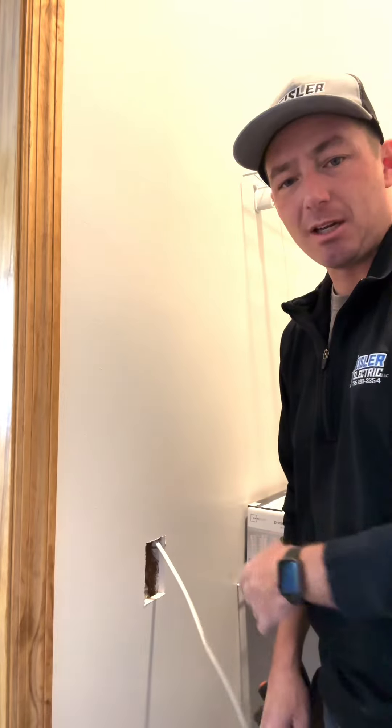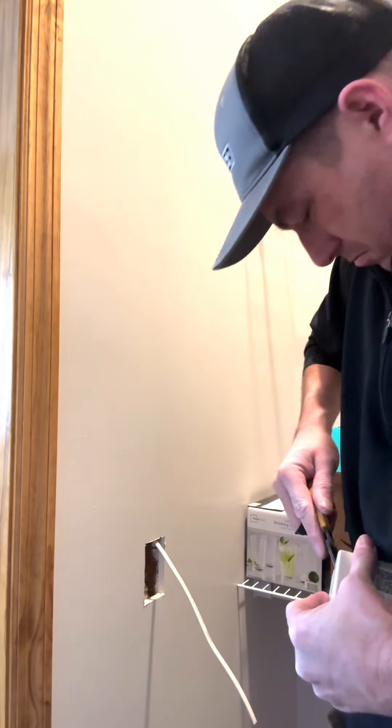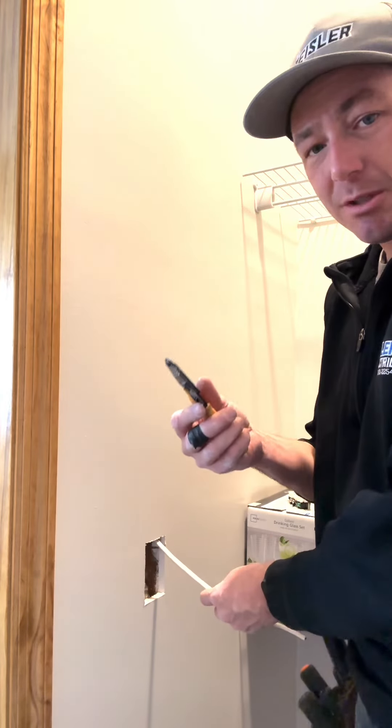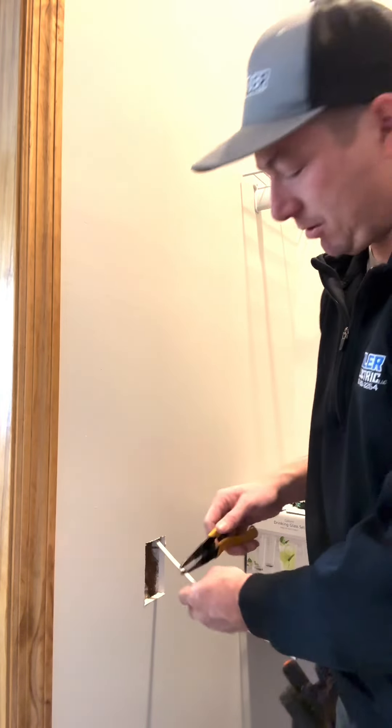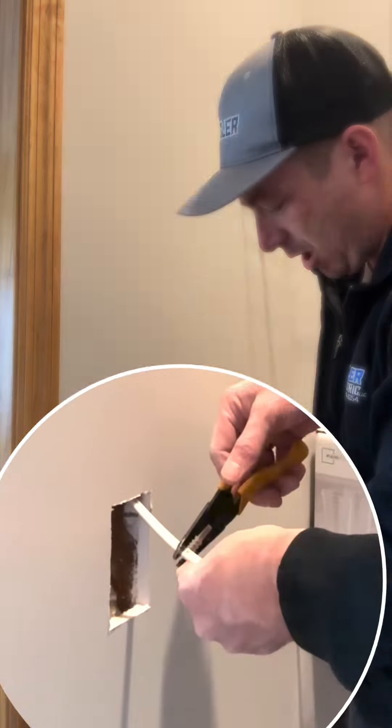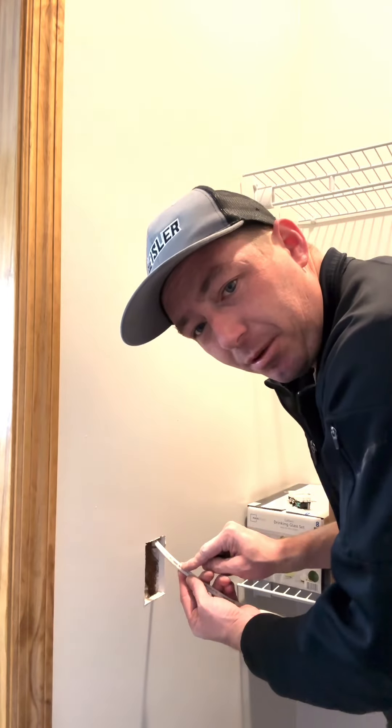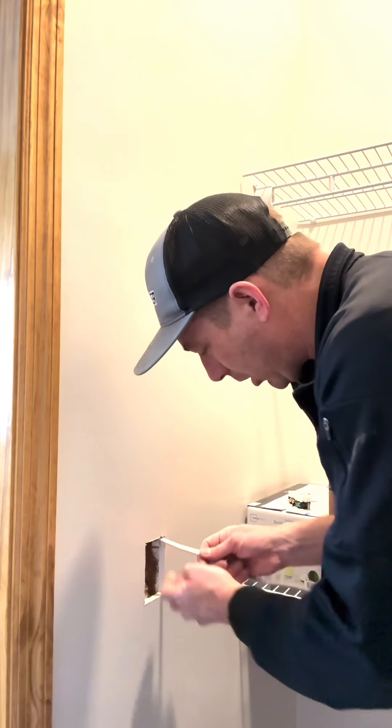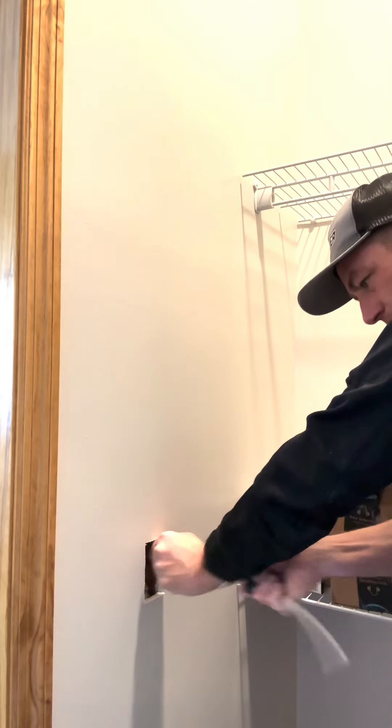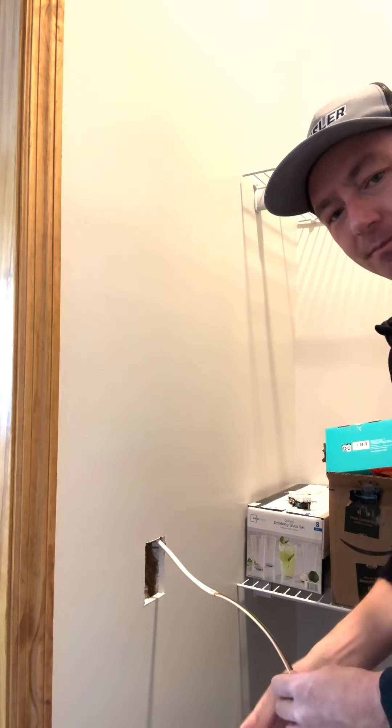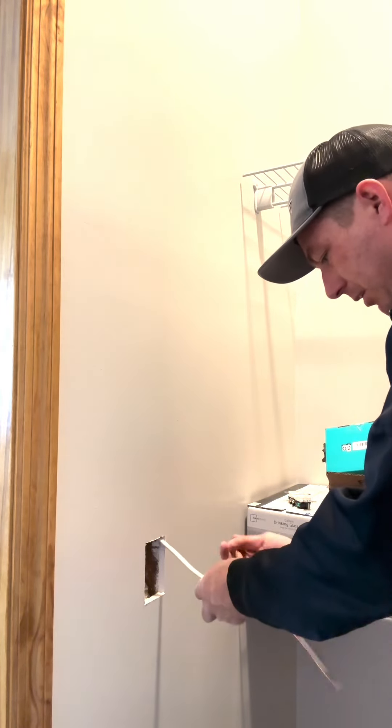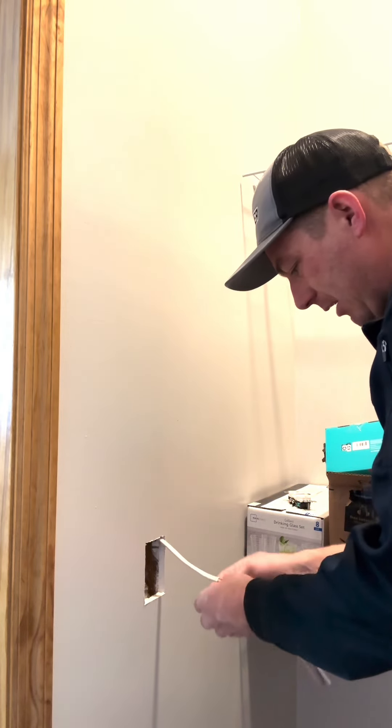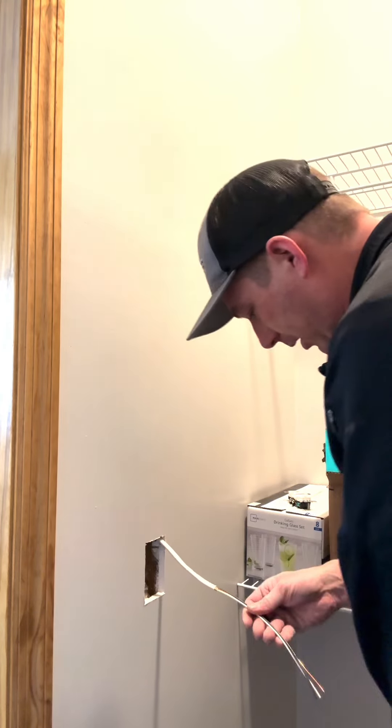Now you're going to watch me do this with my strippers. Remember I'm a professional, I've been doing this for 20 years. All I'm going to do, if you ever strip like this, I'm just going to score this insulation. It doesn't cut through at all, it just scores it, puts a mark on it. So then you can just take it, move it around, and it just breaks right off like that. If you're not comfortable doing that, don't do it because you can short the wires that way.